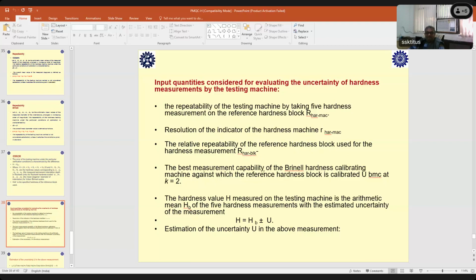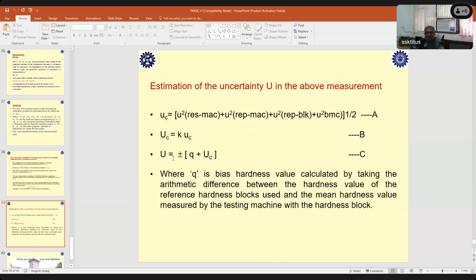And the best measurement capability of the Brinell hardness calibration machine against each reference block is finally given by H equal to HB, that is the average value, plus the uncertainty. And if there is an error component, you can add it to the machine. That is a separate thing, which comes as uncertainty: the error component plus the overall uncertainty.